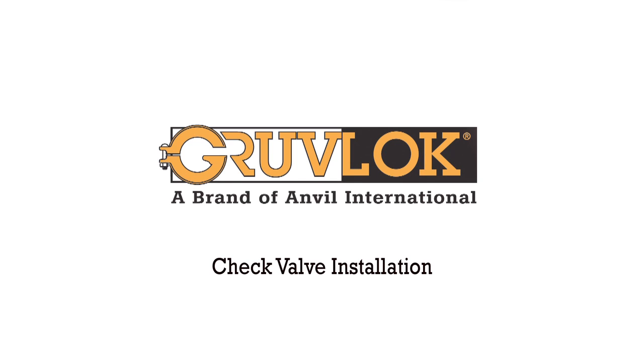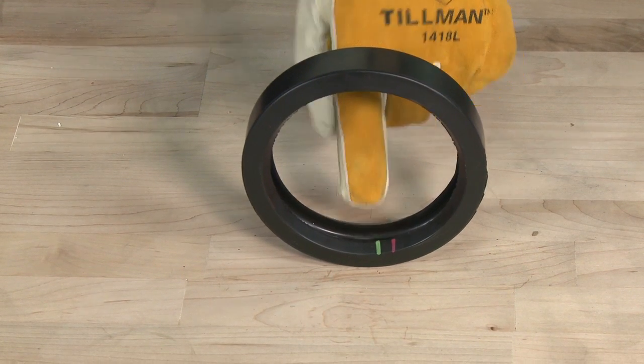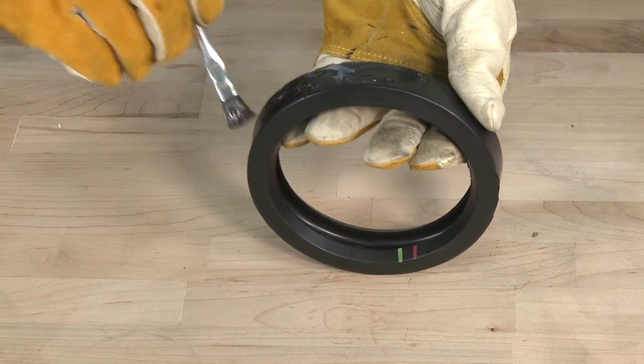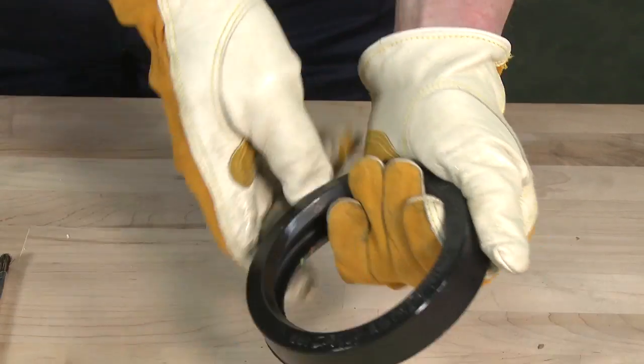7800 Check Valve Installation with RigidLock Coupling. Check the gasket to be sure it is compatible for the intended service. Apply a thin coat of Gruvlok lubricant to the outside and sealing lips of the gasket. Some applications require lubrication of the entire gasket surface.